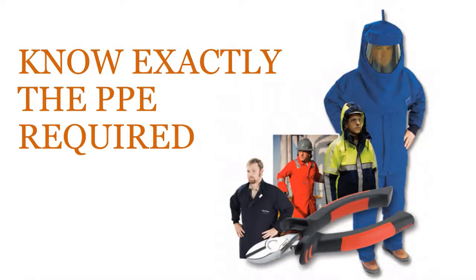There is another way to figure this out, and if you're in Canada, it would be in CSA Z462, or in the US, it's NFPA 70E. In those standards, there's what's called the table method, where you can determine the PPE for a specific job. But the thing is that you don't really know exactly what you're dealing with. It's based on assumptions, and it's fairly conservative. So with the arc flash study, you can pinpoint exactly how much incident energy you're going to need, and that correlates directly with what clothing I need to wear. That's the first thing you get.